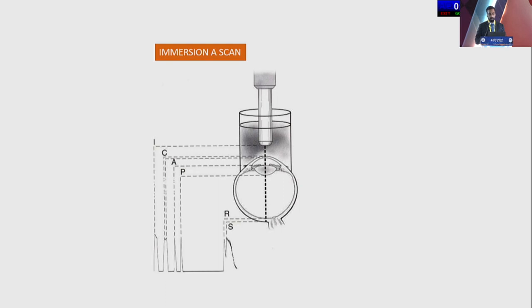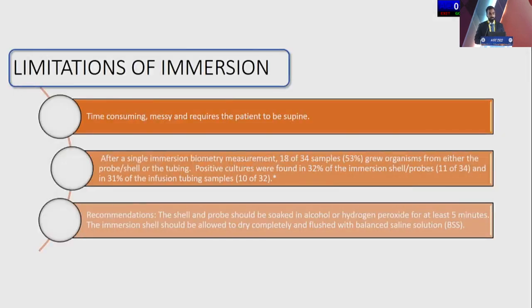So this is your typical immersion A scan. You will see here, since the probe does not come in contact with the cornea, you have an extra wave coming from the probe, and then you can see a double spike coming from the anterior cornea and the posterior cornea. Following which you see the spike from the anterior lens and then the posterior lens. Then you see a line with the vitreous cavity, and then you have the spike from the retina and sclera. So immersion, as I said, works better and gives you more accurate results compared to applanation.